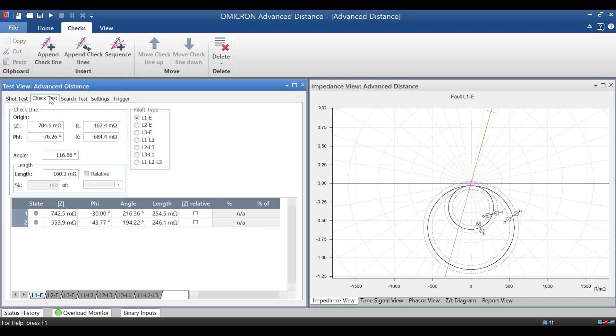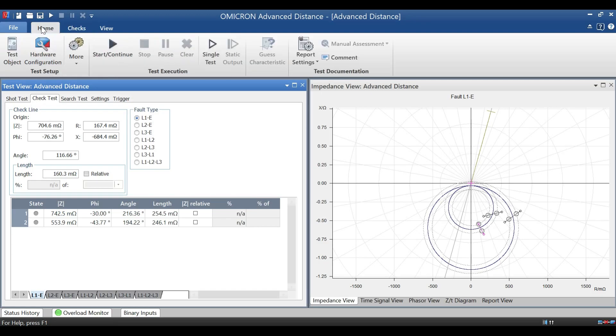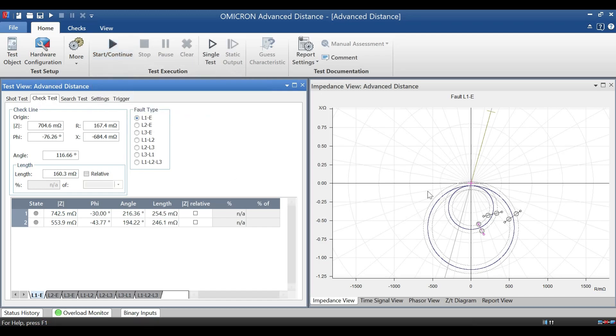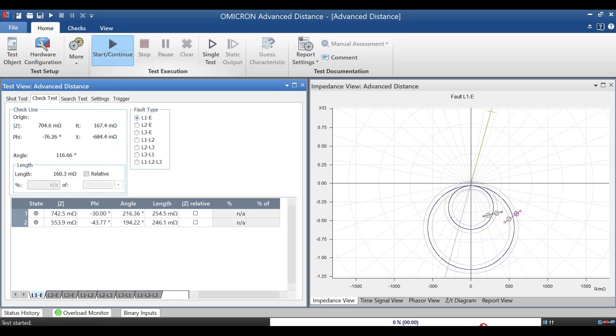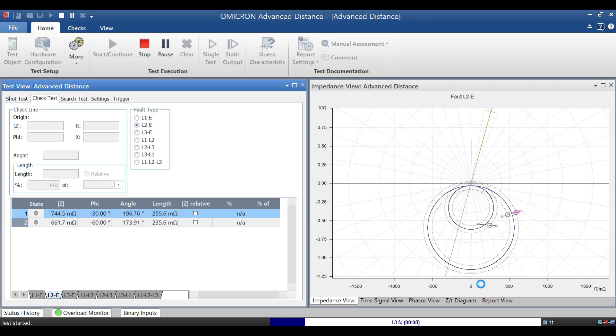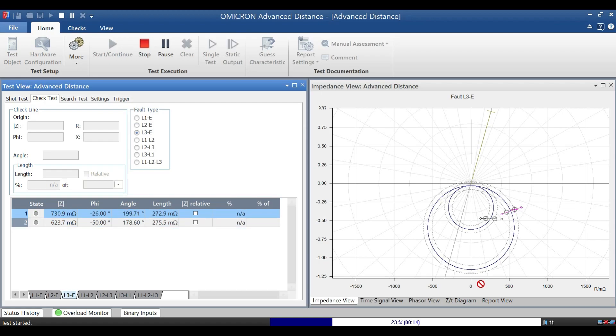Once you finish add selection, then we can go for testing. For testing, in the top side menu, you can able to see run. When you click the run, the kit will start to inject current and voltage to the relay. When you get green plus, that means your test is getting passed. If you get red color indication with cross, then it is getting failure. That means we have to correct some settings, or the graph is not matching with your relay settings.